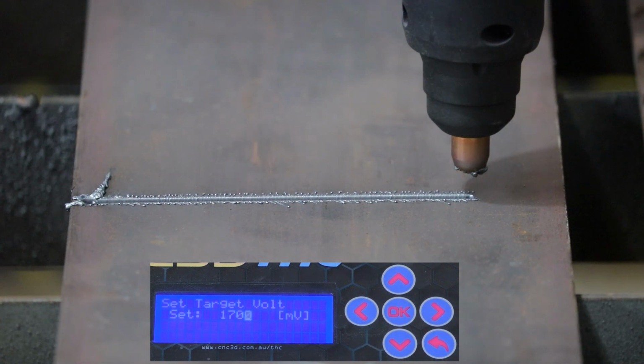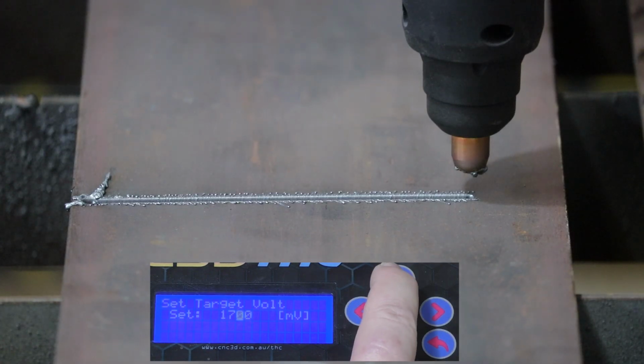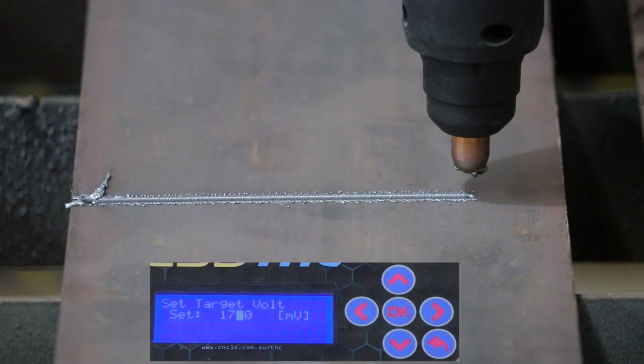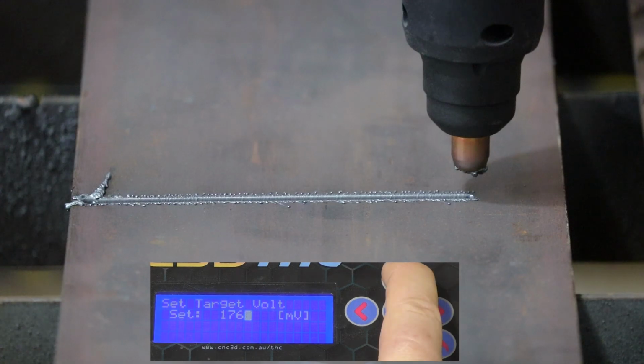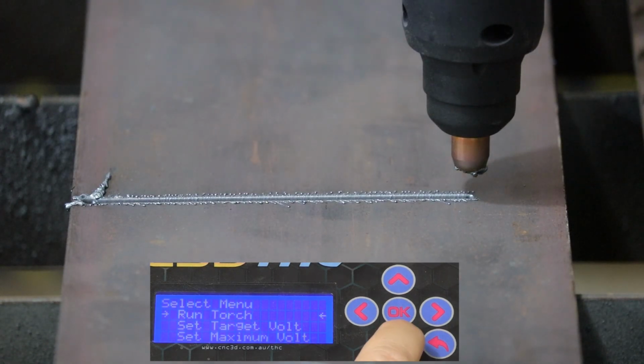We've got it set to 1700 at the moment. If I change this to 1763, I can be super accurate with it. Otherwise, 1700 is a fairly good value. It doesn't have to be 100% exact, but we'll go 1763 anyway. 1763 done. Please wait, which means it's saved. So if I now go down to set target voltage, you will see it says 1763. That's the voltage that we have just set as the target voltage.